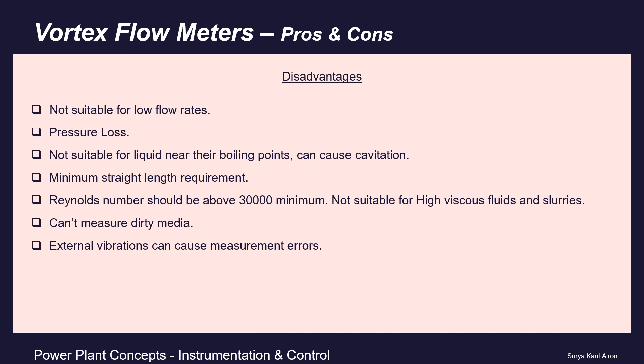Second, vortex flow meters cause pressure loss. Like orifice meters, being intrusive they cause a pressure drop as flow increases, resulting in permanent loss. Liquids near their boiling point could experience cavitation if the pressure drops below the vapor pressure. When pressure recovers above vapor pressure, bubbles implode — cavitation causes the meter to malfunction and should be avoided at all times. A higher minimum straight pipe length is also required upstream and downstream.